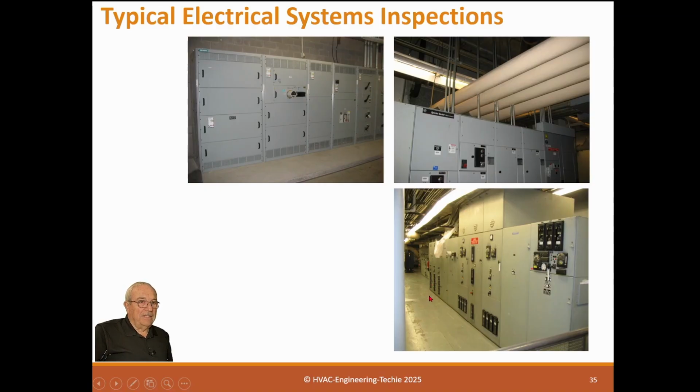And to say I panicked is the correct thing. I said, this is a 4,000 amp. It's on, under load. I ran and grabbed an operator and said, what's happening? This can't be. He said, well, we put plastic up so we wouldn't get it wet. I said, you don't understand. If water, this is right above the transformers, if this water gets in there and this blows up, this will actually take down this high-rise building.